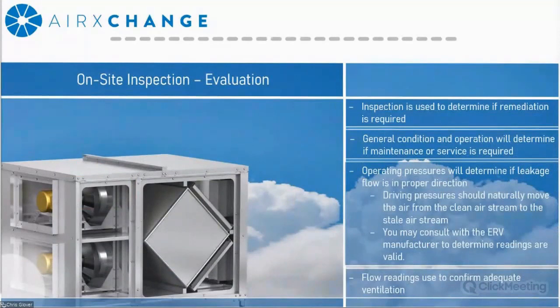Okay, so really the inspection part of the process is used to evaluate whether any type of remediation on the device is required. The general condition is used to determine whether maintenance or service is going to be required. The static pressures are going to be used to determine whether or not changes need to be made to the fan system or control system for the system to operate properly. Once again, make sure that the driving pressures are from the supply side to the exhaust side. After you inspect the unit, if you find that this isn't the case, you'd want to determine the validity of those readings, or consult with the unit manufacturer to see if those readings are consistent with what they would attribute to the system. All the readings are going to basically be used to confirm that the ventilation rate is adequate, and whether or not a further inspection is going to be required, or your system is good to go.